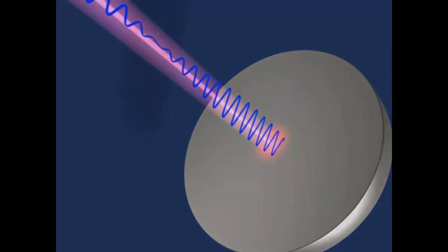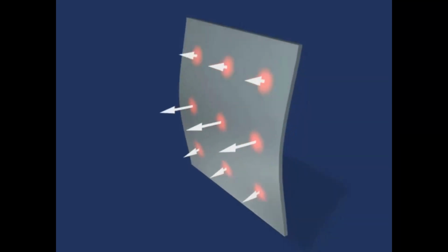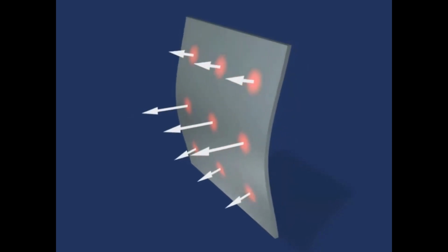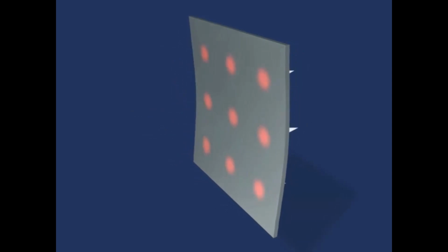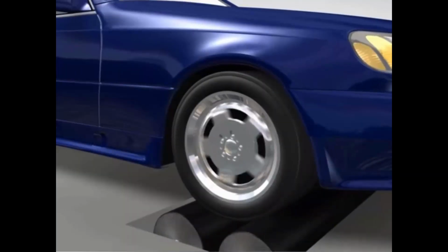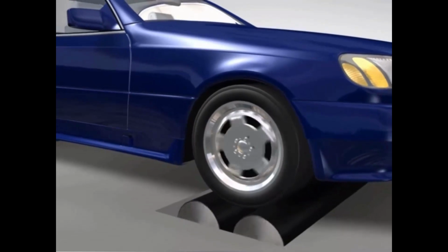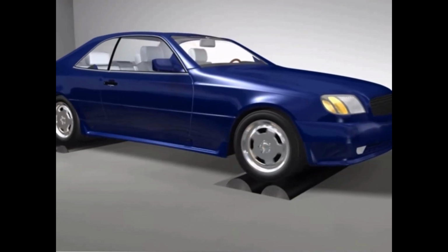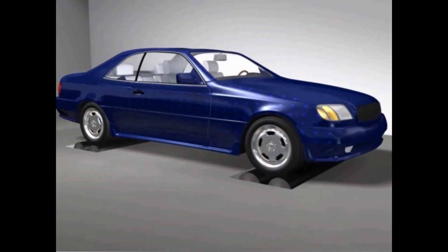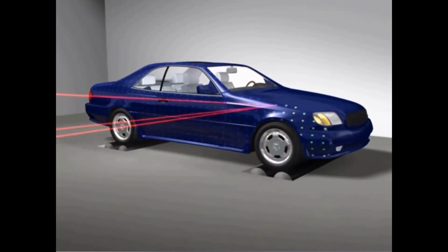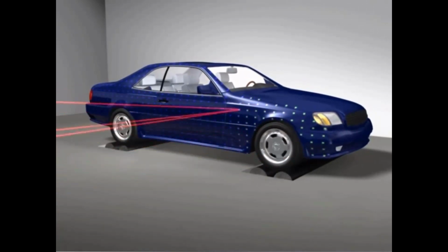Vibratory motion is properly characterized as a true 3D phenomena. A complete measurement using Polytec's 3D scanning vibrometer includes the spatial nature of the motion. Vibration measurements help unravel the critical system dynamics of a test object. The 3D scanning laser vibrometer uses light as the sensor, eliminating the influence of a traditional contact transducer on the test object motion.